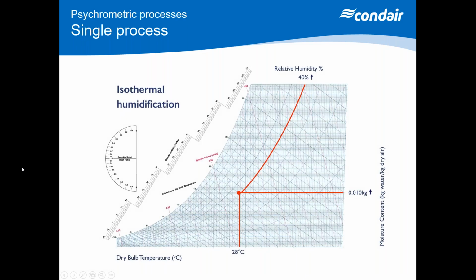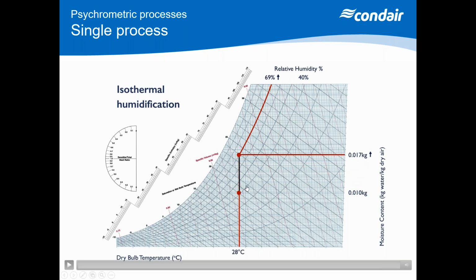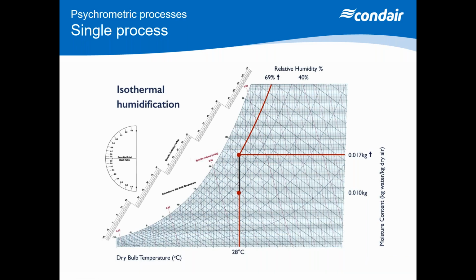Next, a little bit more complicated, is isothermal humidification. So with isothermal humidification, we are putting steam at atmospheric pressure into the air. And when we do that, we have a vertical process line that climbs up the chart. And here you can see you've got an increase in relative humidity, that's 40, 50, 60, 70% RH. You can see that there's an increase in moisture content. That makes sense, we put steam into the air. But interestingly, and a little bit misleadingly, we don't see a change in temperature on this plot. And in fact, the literal definition of isothermal is no change in temperature, like an isobar, no change in pressure. Isothermal, no change in temperature.